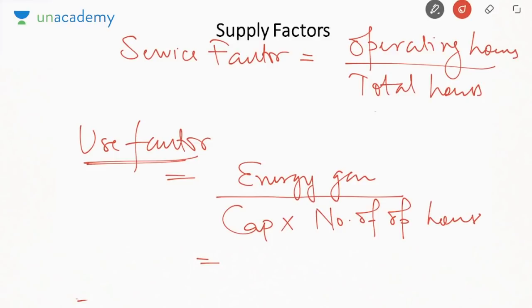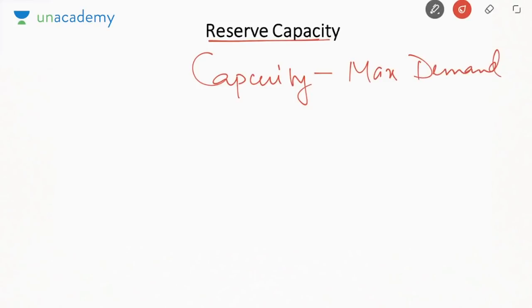And the next is called reserve capacity. Reserve capacity is nothing but the capacity minus maximum demand. So that much power we have in reserve, so that if ever a peak in the demand occurs, or if somehow we have to supply more power, then we must be able to support it. That is why I was telling you installed capacity must always be greater than maximum demand, so that in case of a power surge you must be able to supply that.